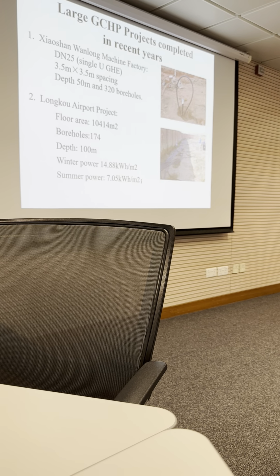In recent years, this is a Xiaoshan Wanlong Machine Factory. You can see the spacing between each borehole is about 3.5 meters. Depth 50 meters. There are about 320 boreholes. It's easy to calculate the total area needed. You see, this is the U-tube inside. Down, up, and we can use a pump to circulate the water into the ground and take water from the ground. Of course, we need to cut it. Then connect to the condenser or evaporator of the air conditioning system. This is the original pipeline.